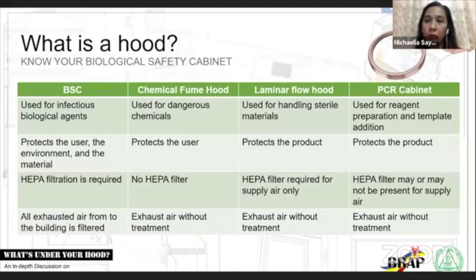Right. Laminar flow hood. This is used for handling sterile material. This is intended just for the protection of the material. It actually makes the cabinet positively pressured, forcing dirty air out. So it feeds the internal chamber of your laminar flow hood with HEPA filtered air. So there are no particles, there are no contaminants, and it pushes air out of the cabinet towards the end user. So if you could imagine you're using a laminar flow hood and you're processing TB cultures, that would be disastrous.